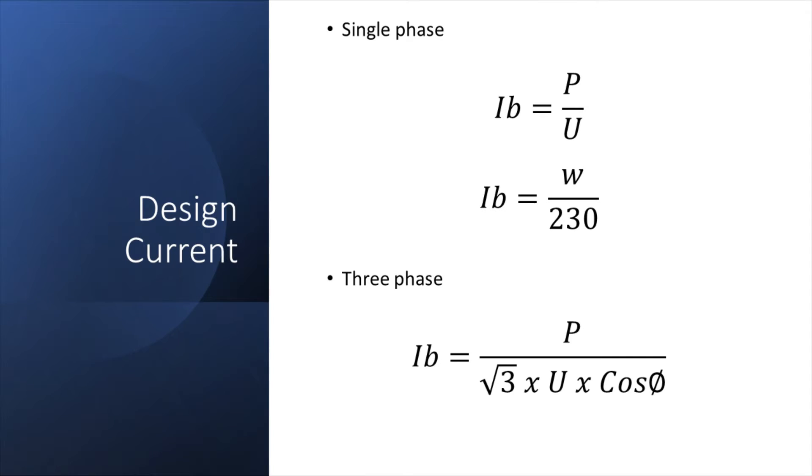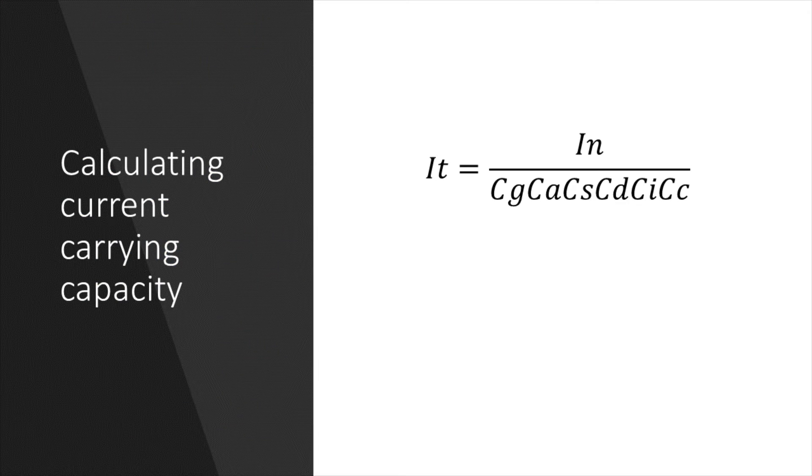First we need to calculate the design current using the calculations on the screen, which I'm sure you'll already be familiar with. Then we can select the rating of the protective device by selecting the device that is either equal to or greater than the design current, and then we can calculate the IZ, the current carrying capacity of the cable, using this formula by dividing the IN by any applicable correction factors.